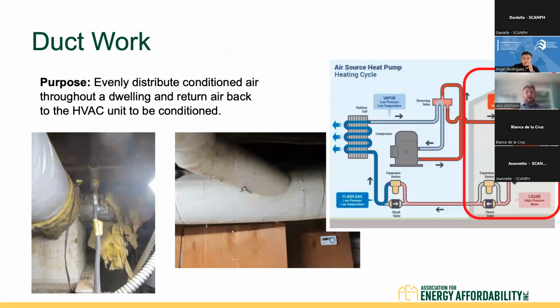So ductwork. The design of ductwork is to evenly distribute conditioned air throughout a dwelling and return air back to the HVAC unit to be conditioned. Here's some photos of some ductwork that is poorly maintained. And then if we're looking at where we are in the building, again, this is sort of in the unit, not really connected directly or within the heat pump technology. It's what is distributed in the air. However, this can affect the efficiency of your equipment. So it's really important to make sure that your ductwork is properly cleaned and inspected. Next slide, please.